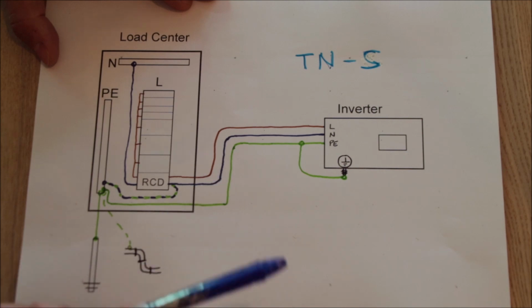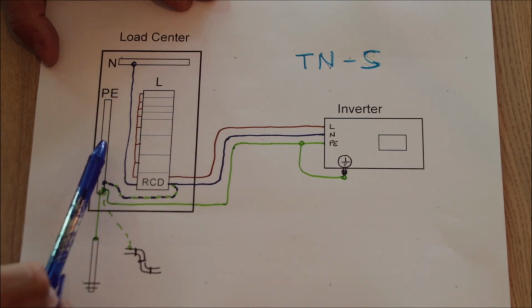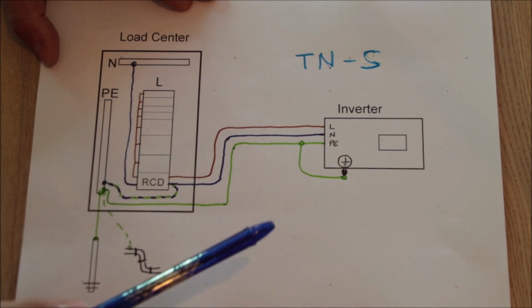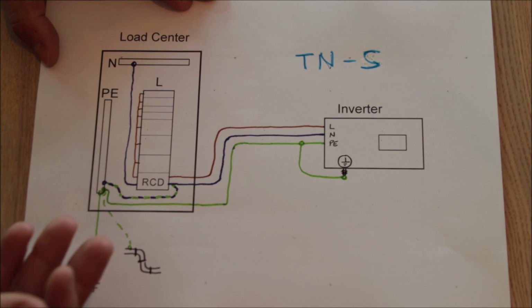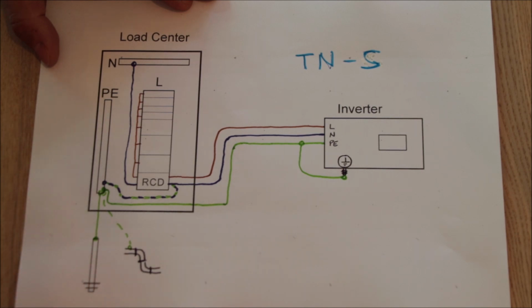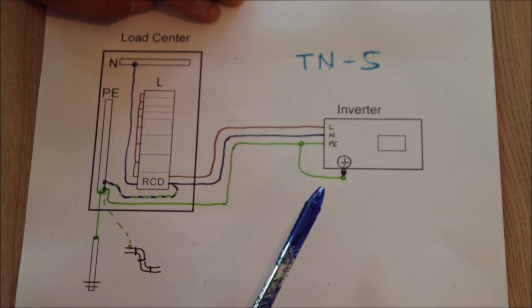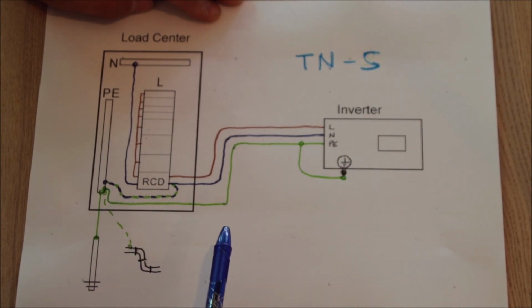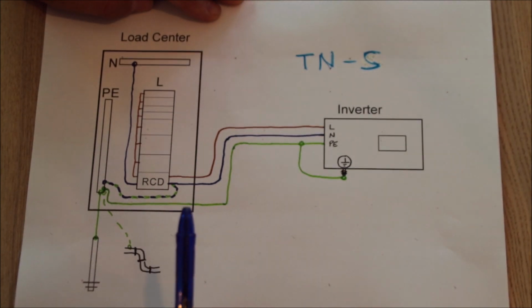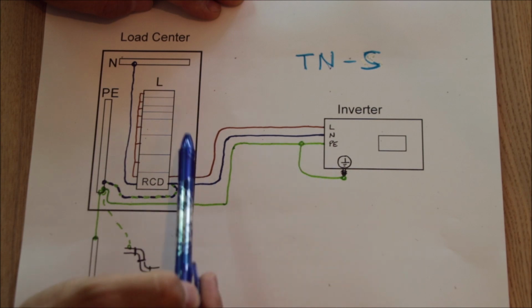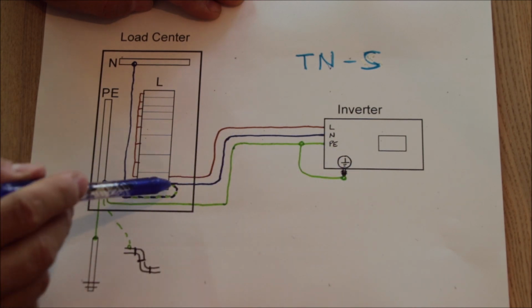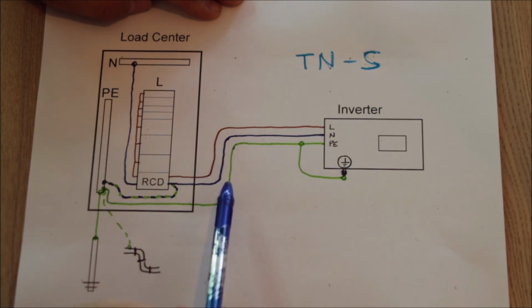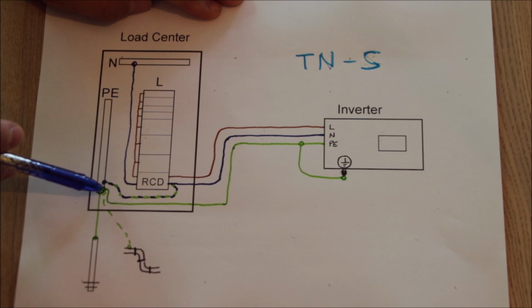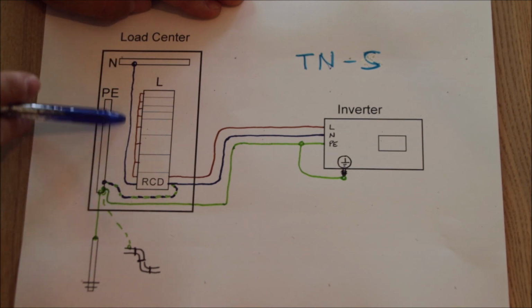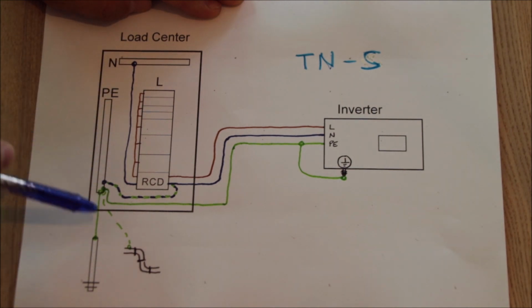And when you build an off-grid system, I'm pretty sure that your load center, your breaker box, will be right next to the inverter, and the rod will be right next there, because you will build this all at one place anyway. So how do we do this? We have our 3 wires from the inverter going to the load center. If you have a split phase, you have 4 wires. But you have your L, you have your N. Those are going straight into the input of the RCD, and you have your PE, which will come from the earthing rod. The earthing rod we will connect at our load center to the PE bar, because that is the solid place where we can do that best.